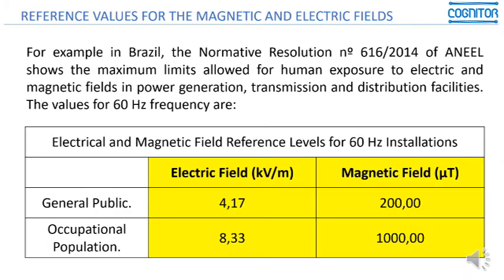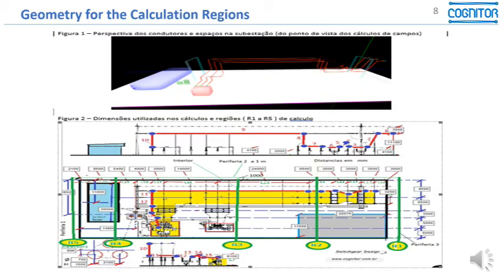When I say general public, I mean people different from substation operators, people which may be walking near the substation and are not skilled people related to electric power. For the magnetic fields, the values are 200 microteslas, and for the occupational population, the values are 1000 microteslas.